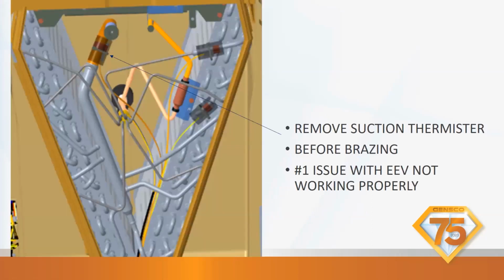Again, that's where the suction thermistor is on the coil. Take the door off, cut the wire tie, pull the insulation tape off, remove the suction thermistor. You can just let it dangle there, put it right back in the same spot, put the insulation back on, and put a new wire tie on. You can see how close that is to that 3/4 or 7/8 line. You are going to melt it. There's just nothing you can do about it. Okay, so take it off. Don't even take a chance.